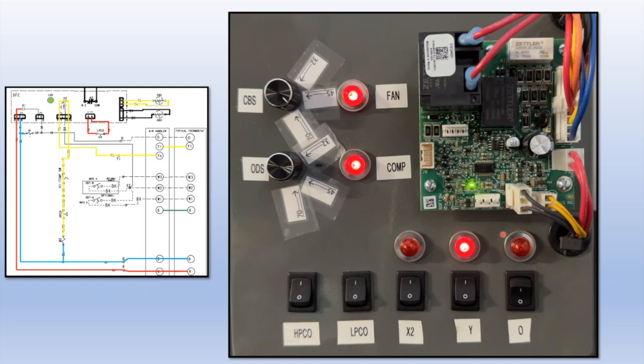If you don't want it to turn the fan on 12 seconds prior to your reversing valve being de-energized, you can cut this soft switch jumper. And if you want it to terminate the defrost at a warmer temperature of 70 Fahrenheit versus 47, you would cut this jumper.